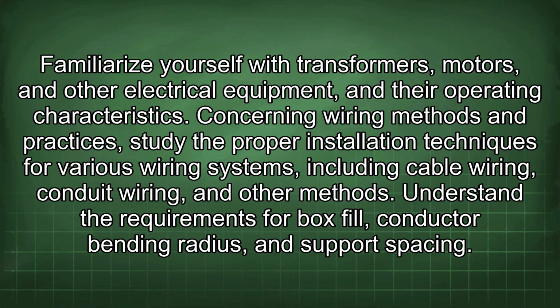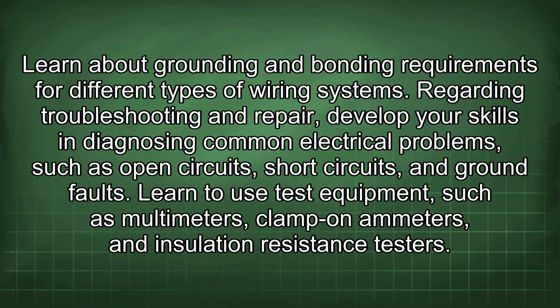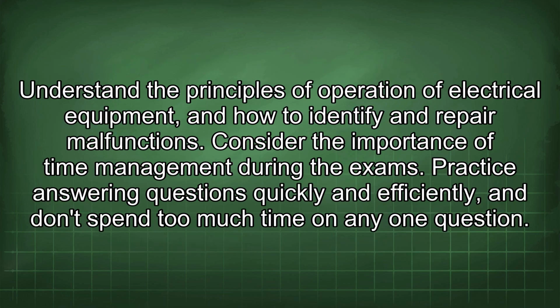Concerning wiring methods and practices, study the proper installation techniques for various wiring systems, including cable wiring, conduit wiring, and other methods. Understand the requirements for box fill, conductor bending radius, and support spacing. Learn about grounding and bonding requirements for different types of wiring systems. Regarding troubleshooting and repair, develop your skills in diagnosing common electrical problems such as open circuits, short circuits, and ground faults. Learn to use test equipment such as multimeters, clamp-on ammeters, and insulation resistance testers. Understand the principles of operation of electrical equipment and how to identify and repair malfunctions.